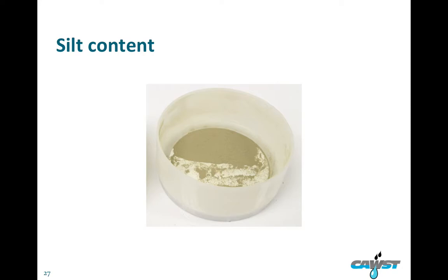But the most important reason why you want to minimize your silt is that what tends to happen with sand that has a high silt content when it's installed is that the first flow rate in your filter is slow, and might meet specs, but then the silt washes out and the flow rate increases. This can have some different consequences.